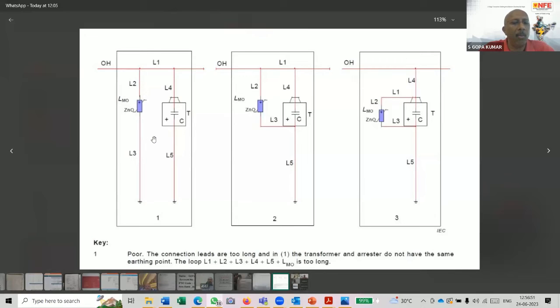Now, connection number one, for extra high voltage, let's say 66 kV, 132 kV, 220 kV, it may work because the lead length is only 5 or 6 meters. And the withstand voltage of a transformer at that voltage is very high. Whereas for 11 kV or 22 kV transformers, the impulse withstand voltages are quite low. It's not in hundreds of kVs. It is much less. Let's say an 11 kV transformer, it's about 75 kV. So a 5 meter wire length itself is a problem.